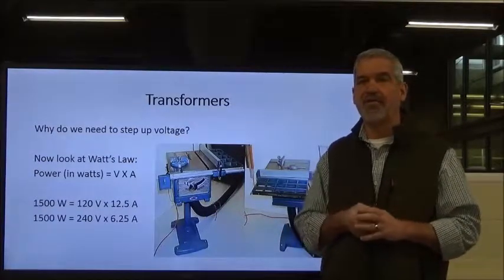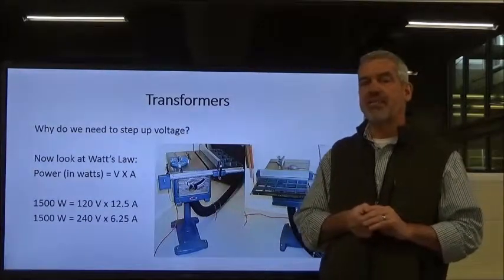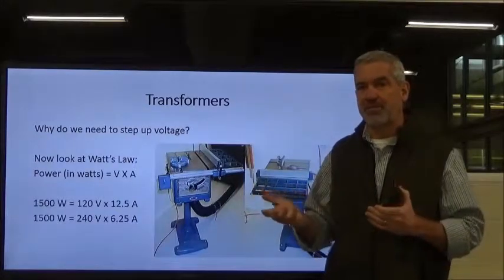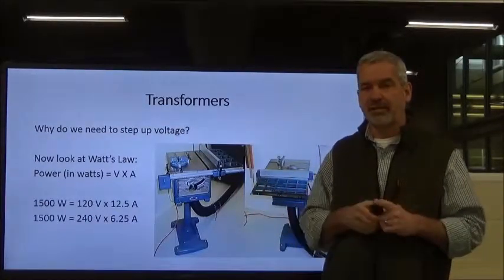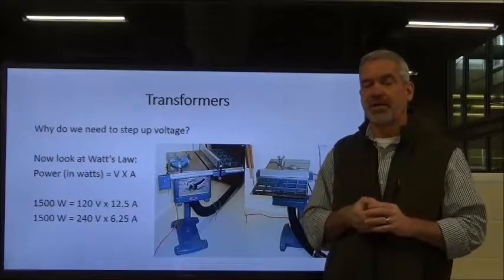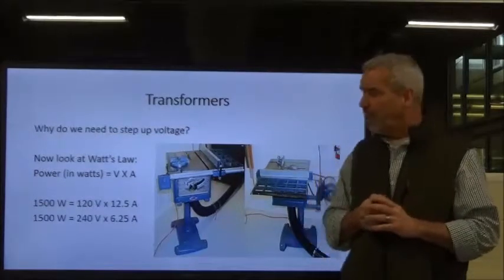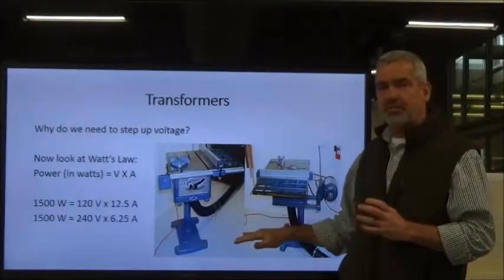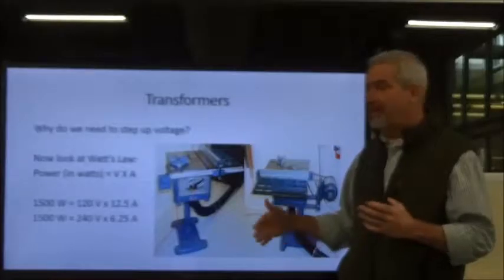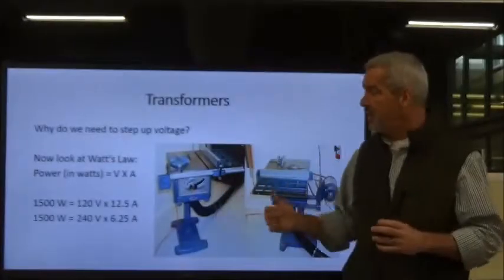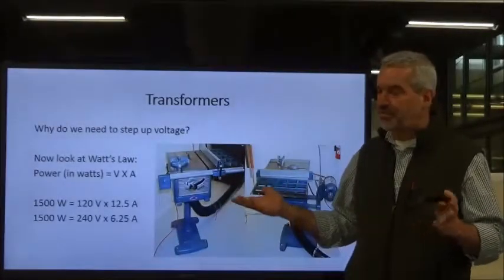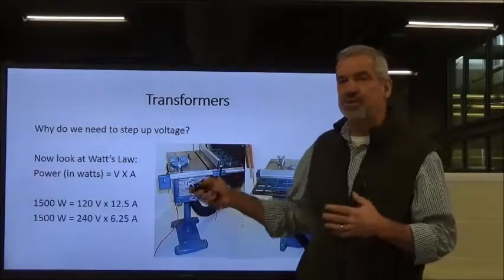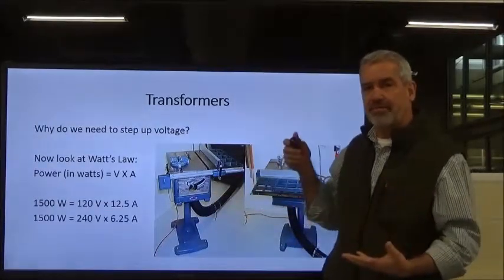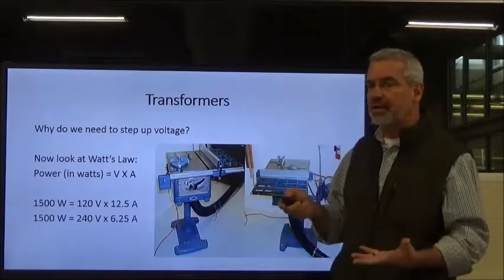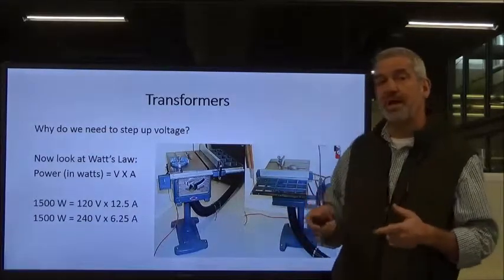It cut the inrush current in half. Instead of my 15 amp circuit breaker tripping at 120 volts, I got a 15 amp double pole breaker and was able to drop the inrush current by half. Now I have no tripping problems whenever I start the saw. That's a great saw, and it was just an example of the inversely proportional concept we were discussing with power.